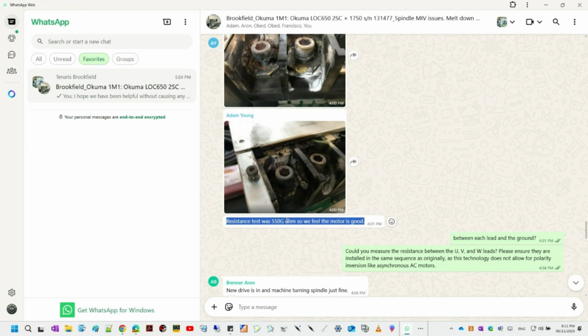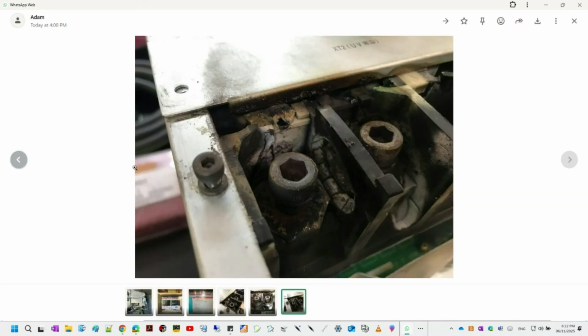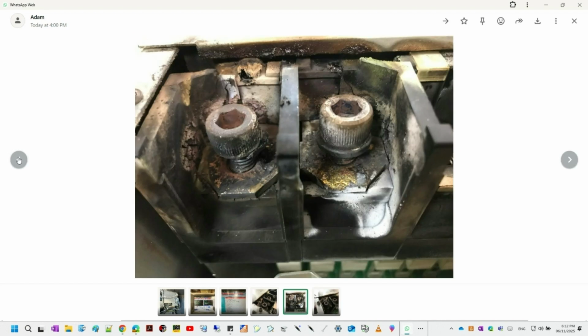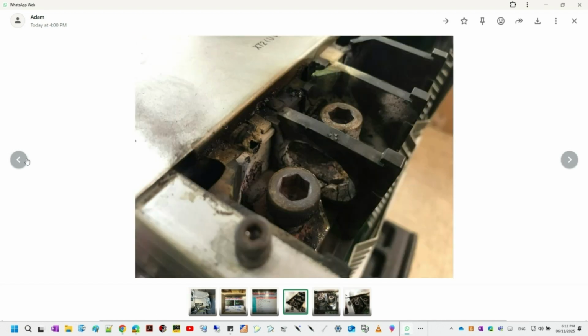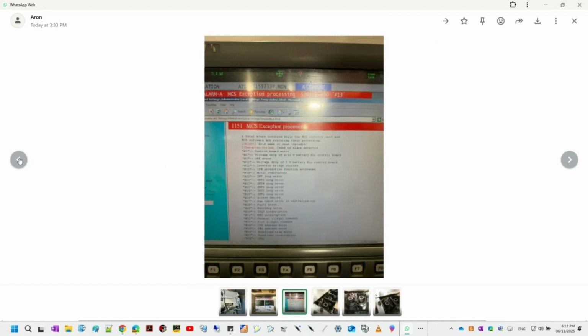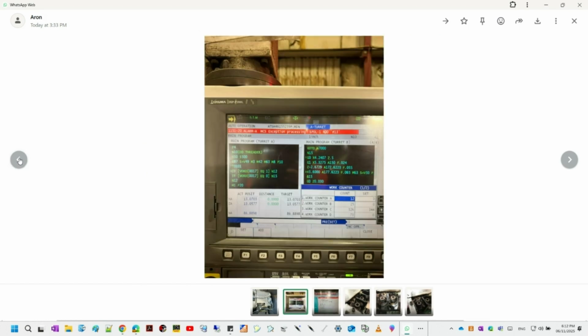Yeah, one key alarm they noted early on was 1151 ALARM-A MCS Exception processing. When they cross-referenced that with the Okuma Troubleshooting Guide, it pointed specifically to code #13, which indicates the IPM protective function was activated. IPM, Intelligent Power Module. You got it. The core power switching component within the drive itself. So the machine's own alarm history was already pointing towards an internal drive issue related to its main power components, even before they saw the worst of the damage.